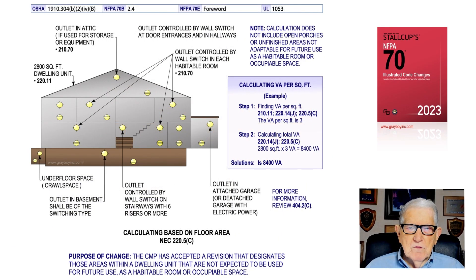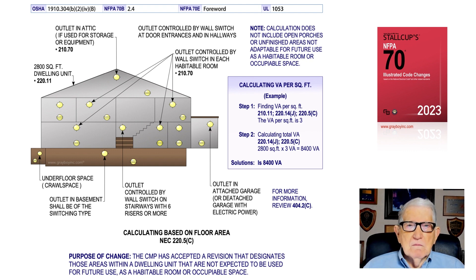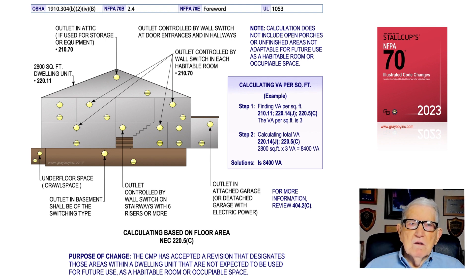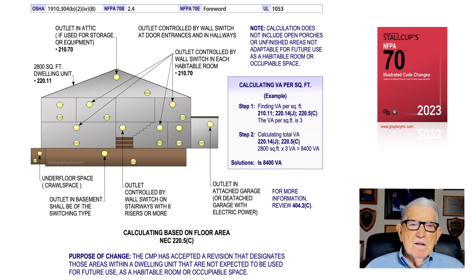This illustration deals with calculating loads based upon the floor area in accordance with NEC 220.5(c). The purpose of this change is to define the area that must be used to calculate the loads. The note reads: the calculation does not include open porches and unfinished areas not adaptable for future use as habitable rooms or occupied space. Those areas are not included in the calculation. In the calculation we have a 2,800 square foot dwelling.